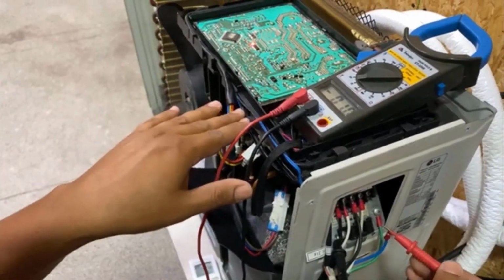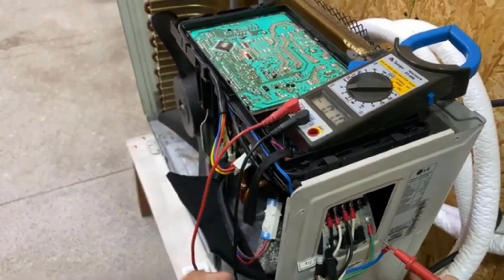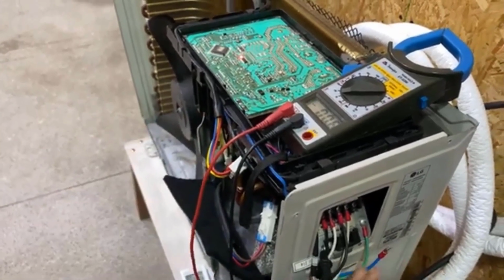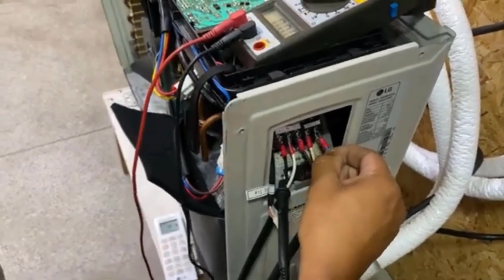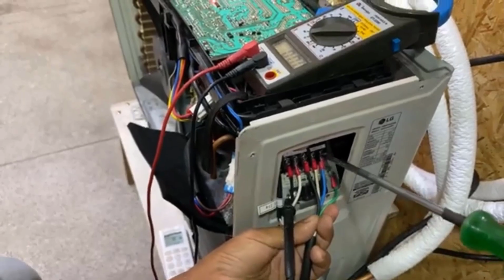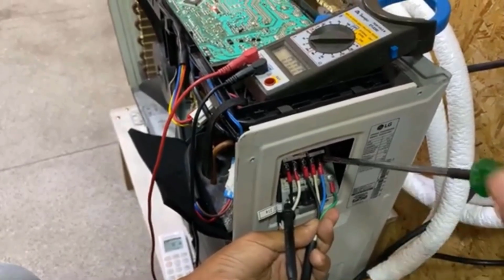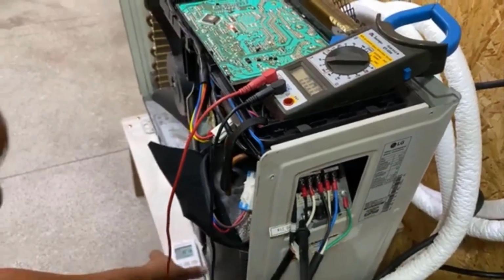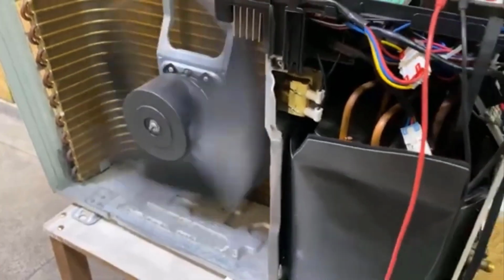Electronic faults. Damaged electronic board: electronic components on the evaporator or condenser board may be burned out or malfunctioning. Incompatible or corrupted firmware: in some modern models, the board software may be outdated or corrupted. External interference: voltage spikes and fluctuations in the electrical network can damage electronic components and affect signal exchange. Electromagnetic interference: nearby equipment such as motors or generators can cause signal interference.